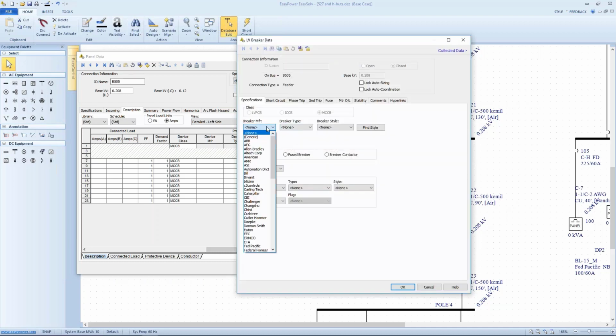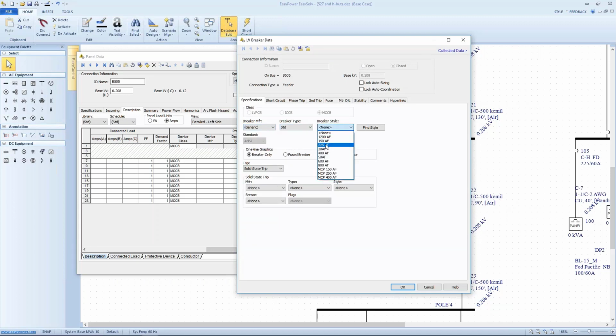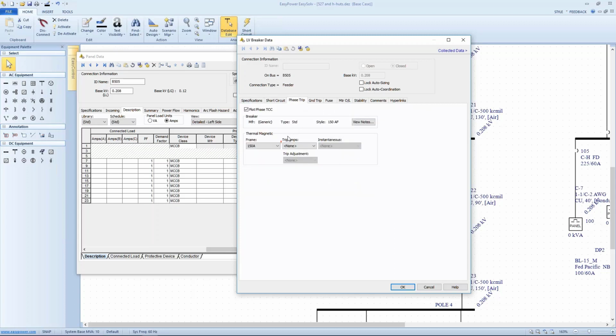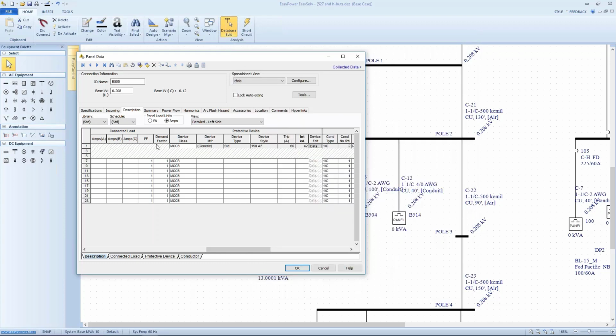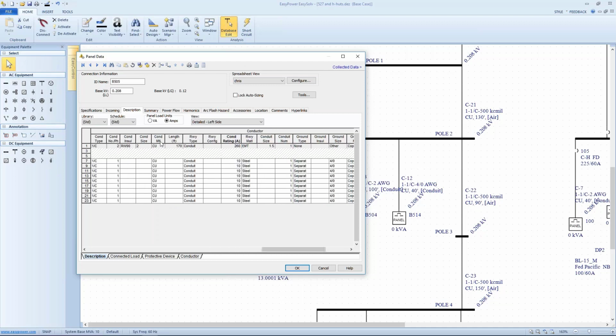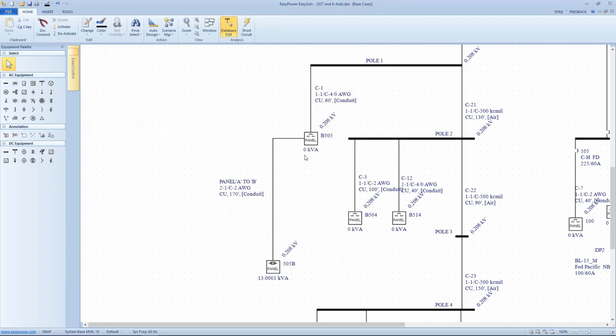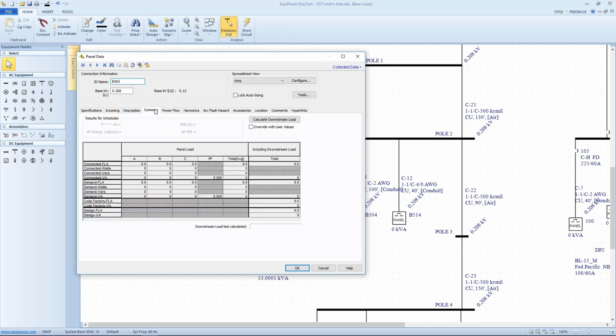And so we set up the breaker that's going to be feeding that panel. So let's set it up with 150 AF. And this would be exactly like setting up a freestanding breaker. So now that I've got my breaker set up here, you can see that the tool pulled in the conduit and cable ratings for that downstream breaker. Now that I've done that, before I close out this panel, I want to go to summary. I want to calculate downstream load. And now it pulls in the load that we have from that downstream panel.